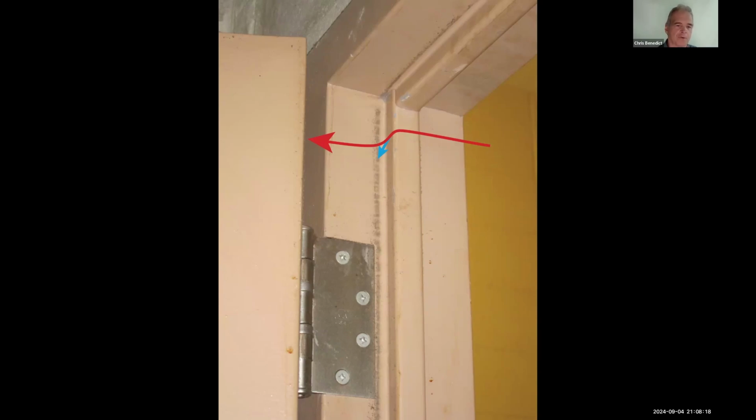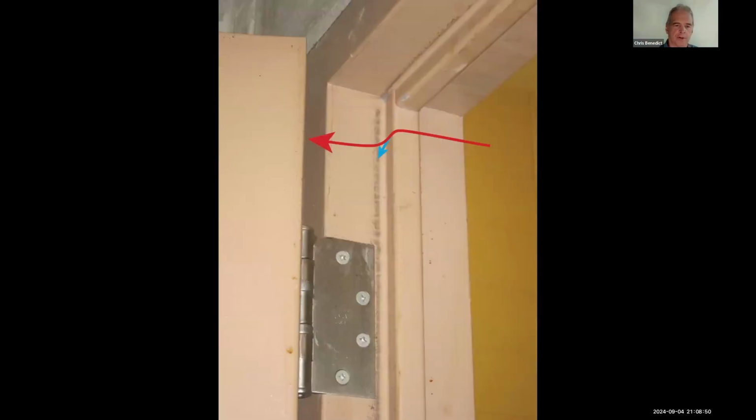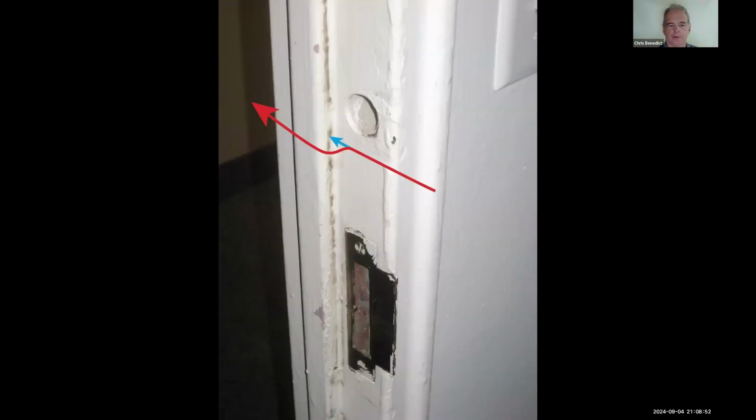So if you saw two streaks, one just to the right of the one you see, then it would tell you the air leaks both directions equally. That is, if the air is equally dusty in both airstreams, though indoor air is usually more dusty than outdoor air, so who knows? It's kind of impossible for indoor air to be cleaner unless you're filtering it, which is another story. So here's dust streaked air. This one was going out. This one was going in toward the hinge. This air is leaking out, so this is probably an upper floor.